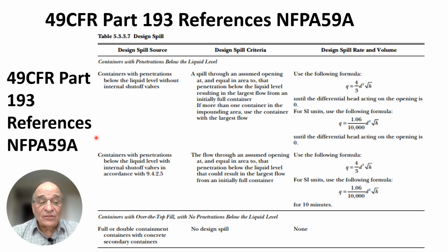For a tank with an internal tank valve, and it should say with internal, here it is, with internal tank valve in accordance with this, you have the same calculation. However, that calculation is limited for a period of 10 minutes. Now, you can actually get a waiver to go below 10 minutes, but you have to be able to prove that your equipment is such that it would shut down quicker than 10 minutes. I don't know of anyone who has pursued that ability to go below 10 minutes. So essentially 10 minutes is given as your design spill for tanks that have internal tank valves.